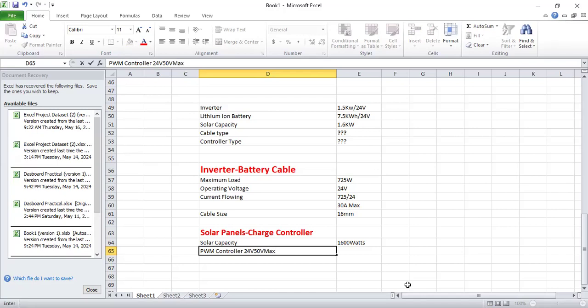So if we're going to use this particular solar charge controller, a 24 volt MPPT controller that accepts PV voltage not higher than 50 volts, it means if you connect your solar panels to it, the voltage shouldn't exceed 50 volts. We want to deliver the maximum current, with the maximum voltage being 50 volts.